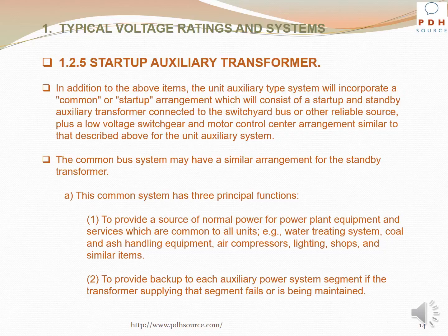In addition to the above items, the unit auxiliary type system will incorporate a common or startup arrangement, which will consist of a startup and standby auxiliary transformer connected to the switchyard bus or other reliable source, plus a low voltage switchgear and motor control center arrangement similar to that described above for the unit auxiliary system. The common bus system may have a similar arrangement for the standby transformer.